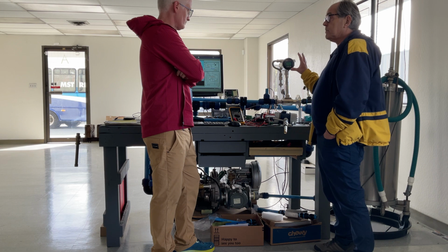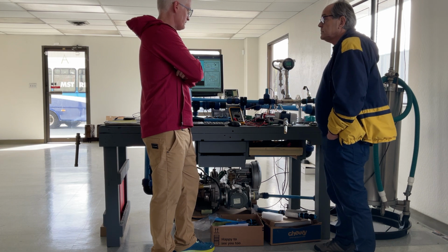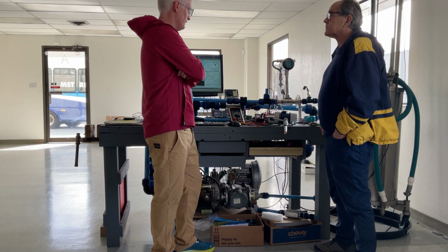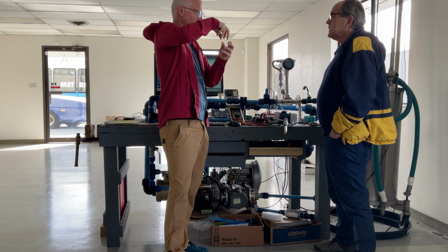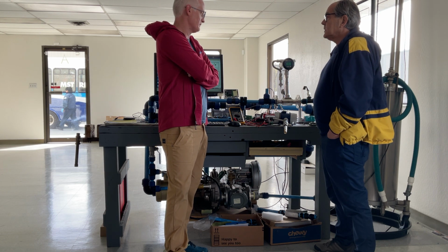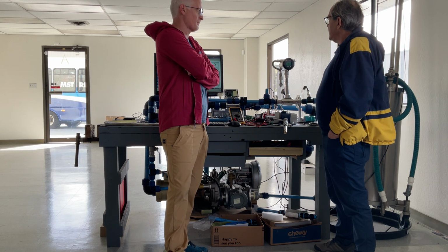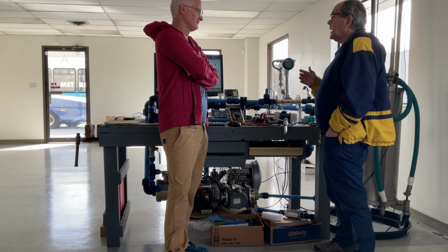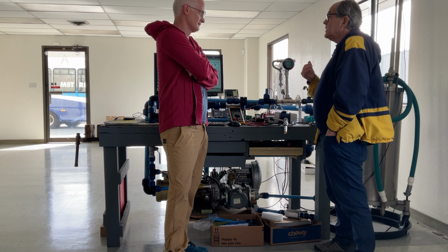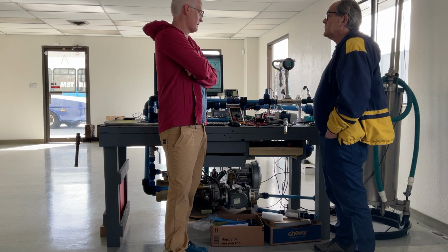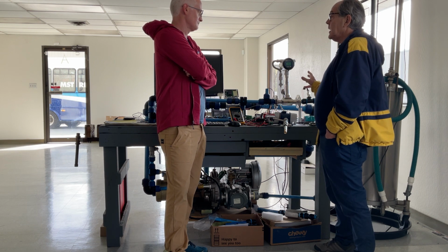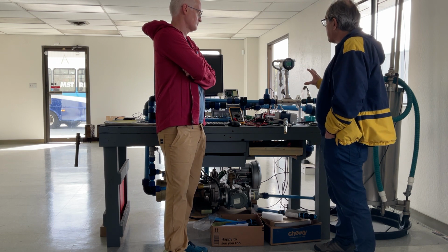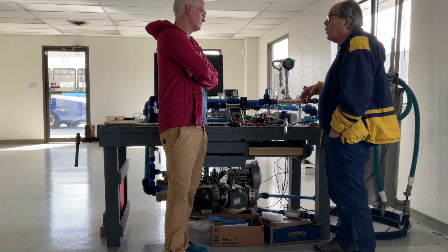That's like the bomb. Let me be the devil's advocate here and say that I feel like different liquids would have different vortexes created by the same thing in the middle. Wouldn't a slurry have a different vortex than water? Yeah, and we know the shedding frequency is a function of the velocity for that fluid. So there's some calibration based on the density of the fluid. We calibrate these with water, and you could tell us some of the properties like blood or oil.